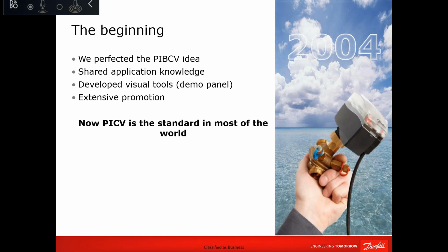So since long back, we came up with the PICV concept, and I will not say we perfected the PICV as Danfoss. I would say we know what the PICV should be and how it should work. So that's why we designed the most optimum way to operate a PICV. There are different technologies, but we believe that we try to minimize all the risk, all the problems in control, system service, etc. And that's why we went to the next step, which is the actuator.